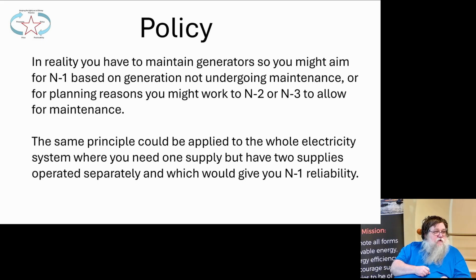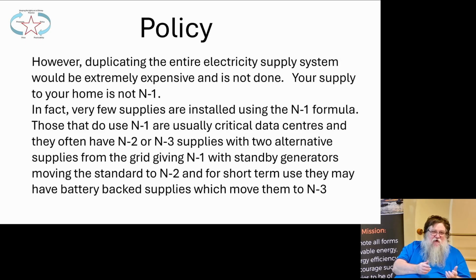Hands up who's got 2 electricity supplies to the house. Nobody. So you've got 2. Well, have a sort now, yes, but you've not got 2 coming from the main supply, no. And very few people do. Some businesses do. It's just too expensive. We don't do it. We don't duplicate everything. Your supply to your home is not N-1. Very few supplies are installed using N-1 formula. Those that do are usually things like data centers at banks and things like that. And they might have N-2, N-3 for their supplies, because they might have 2 mains power supplies, plus standby generators, plus quite often they've got batteries that'll run them while they get the standby generators up and so on.